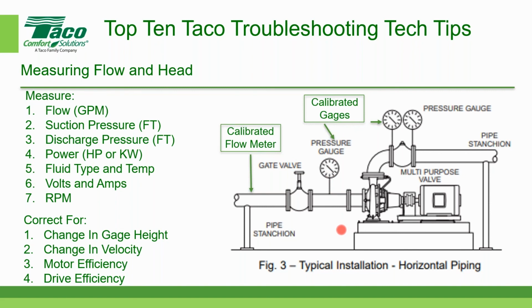I said, well, none of this makes any sense. And that's when I went back to the photographs, and sure enough, the photographs revealed that the gauge was at a different height. So you do have to make that correction for gauge height. We've already talked about the change in velocity. You have to make that correction. You have to know the motor efficiency and the drive efficiency if you happen to have a variable frequency drive. So those are the cool things that you need to know.